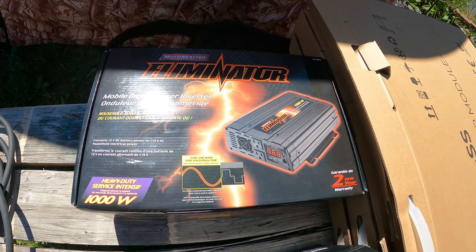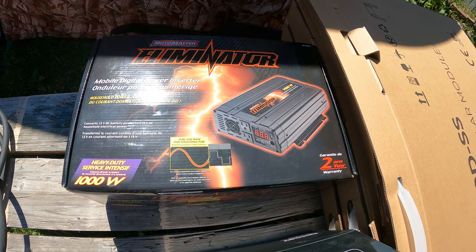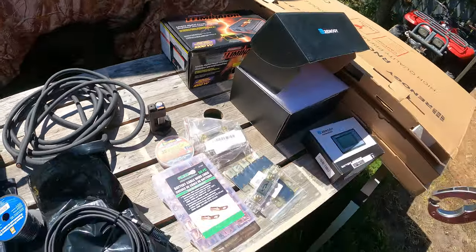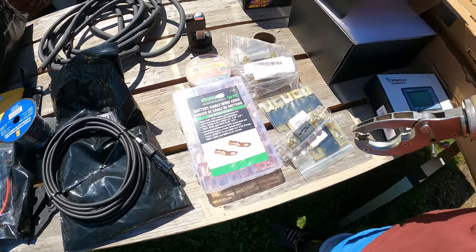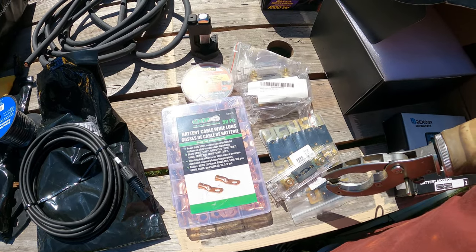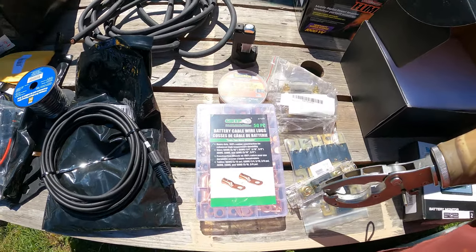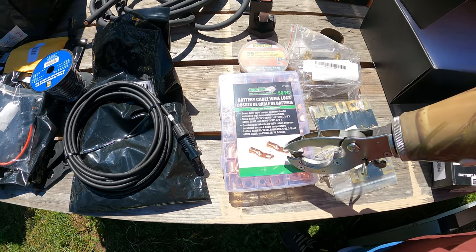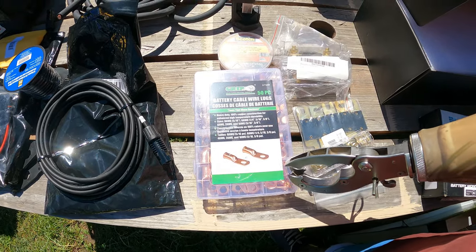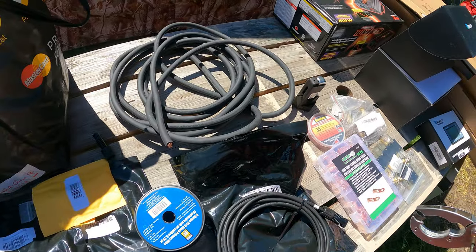For an inverter, we're going with the MotoMaster Eliminator — I said earlier it was 2 kilowatts, but it's actually a 1-kilowatt inverter, which should handle our minimal power needs well. If it doesn't, we can always upgrade. To install all this gear you need ANL fuses or breakers — I initially was going to go with breakers and then switched over to ANL fuses. You need various sizes to protect your various wiring sizes throughout the system, and you'll need copper lugs — make sure they say 100% copper, not copper-clad aluminum.